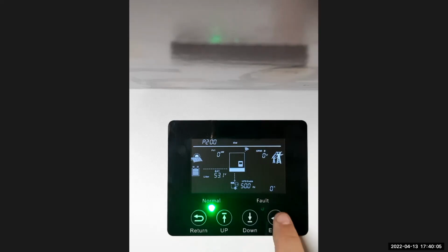The other piece is just different time frames. You can enter different time intervals where you want to use Eskom and not your batteries or panels. So then you run through all your end and start times. And that's basically it for number 15. Number 16 is my hybrid setting. That's where AC and PV can take load. Most of the time, the setting will be disabled. As I said, it will backfeed.